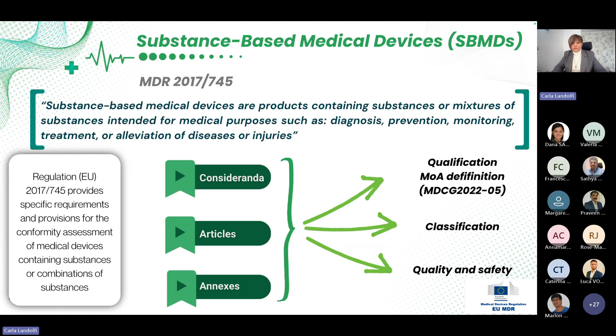First of all, the mechanism of action. This is absolutely essential because for these products, as for all medical devices, it must be mechanical, not pharmacological. The MDR is very clear. If the primary effect is achieved through pharmacological, immunological, or metabolic means, the product becomes a medicinal product. So, ophthalmic substance-based devices must act through a physical mechanism of action, such as forming, for example, a protective film on the ocular surface. This also means that the formulation has to fully support that mechanical mechanism and must not introduce ingredients with pharmacological activity.